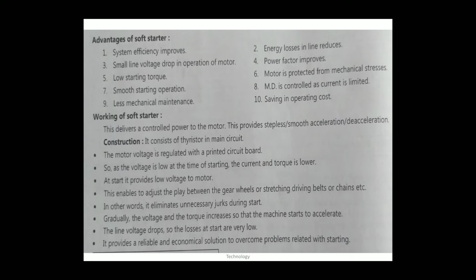This enables adjusting the play between the gear wheels or stretching driving belts or chain, etc. In other words, it eliminates unnecessary jerks during start. Gradually, the voltage and the torque increase so that the machine starts to accelerate. The line voltage drops, so the losses at start are very low. It provides a reliable and economical solution to overcome problems related with starting.